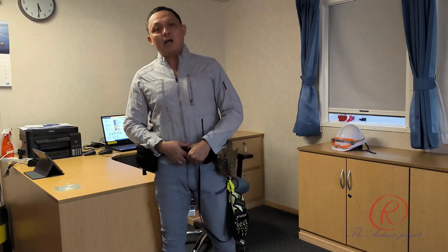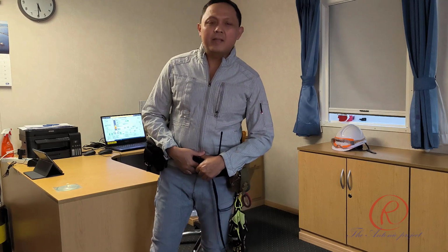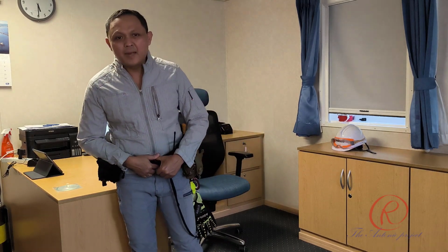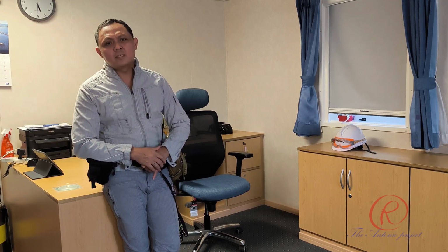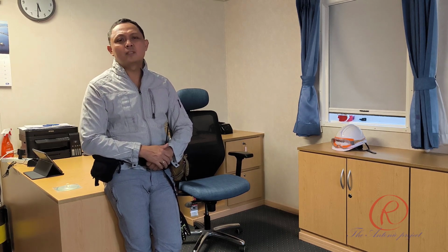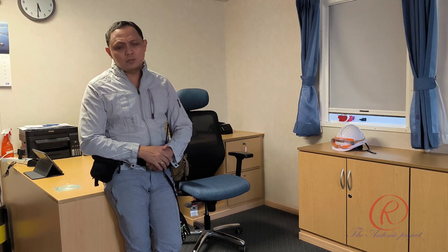In this video, I will share how to maintain a high voltage alternator. The maintenance is as follows. 1. Measurement of insulation resistance of alternator stator coils. 2. Measurement of insulation resistance of high voltage cables. 3. Measurement of insulation resistance of exciter. 4. Measurement of clearance between alternator, rotor, and stator. 5. Testing of alternator cooler leakage alarm.